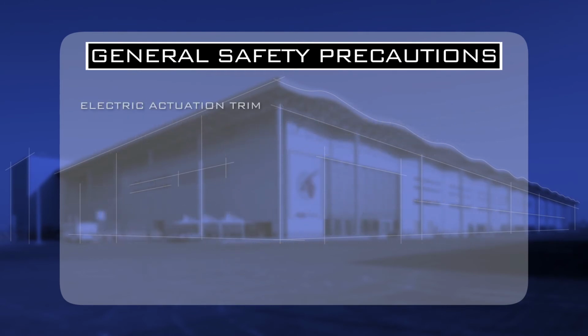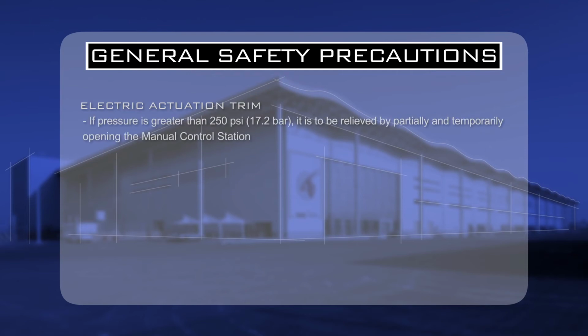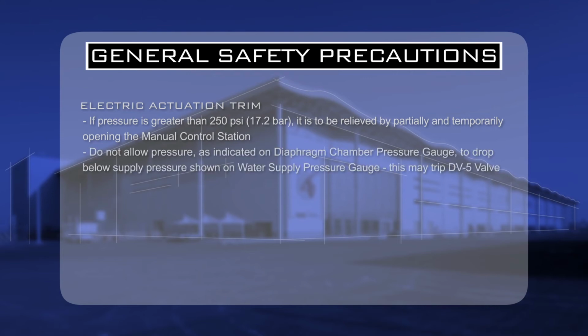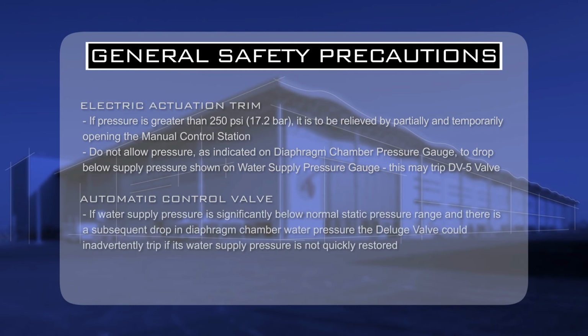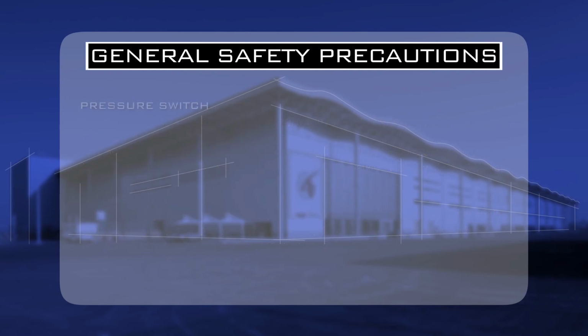The electric actuation trim. If pressure is greater than 250 psi or 17.2 bar, it should be relieved by partially and temporarily opening the manual control station. Do not allow pressure on the diaphragm chamber pressure gauge to drop below the supply pressure shown on the water supply pressure gauge. This may trip the DV5 valve. The automatic control valve. If water pressure is significantly below the normal static pressure range and there is a subsequent drop in the diaphragm chamber water pressure, the deluge valve could inadvertently trip if its water supply pressure is not quickly restored.